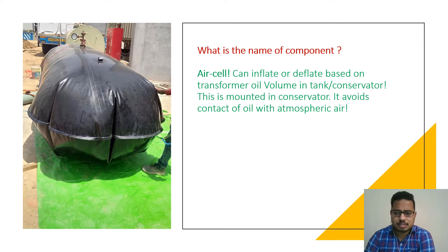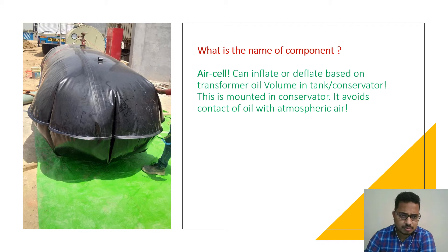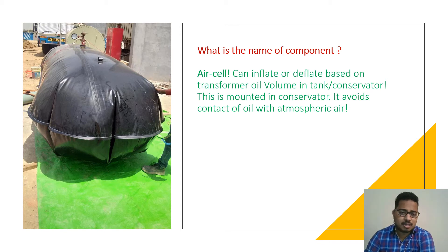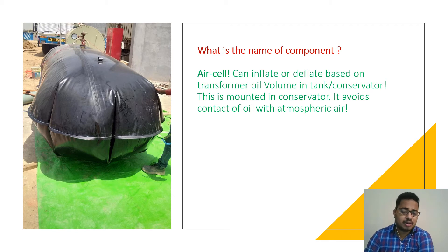This component is mounted in the conservator. It avoids contact of oil with the atmospheric air. The backside portion is the conservator — this will be placed inside the conservator. Whenever loading on the transformer changes, oil may contract or oil may expand due to heat content in the transformer.